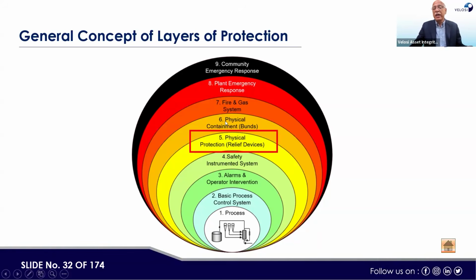If something leaks, the fire and gas detection system can detect that. Then the plant emergency response plan, where the operators or plant management would act in case of emergency. The last one is community emergency response, like civil defense, hospitals, and district management. Those people can also provide help. So altogether, there are 9 layers of protection, and what we are addressing today is the fifth layer of protection, which is called PSVs or relief devices.